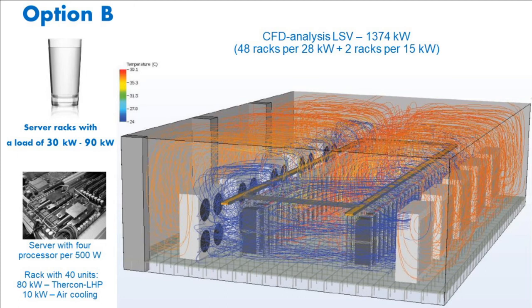There is also a solution with loop heat pipe that allows you to remove up to 500 watts from one processor. When placed in a single rack, 40 servers with 4 processors in each server, 80 kilowatts may be removed from one rack using loop heat pipe and another 10 kilowatts using air cooling. I will talk more about this solution later.